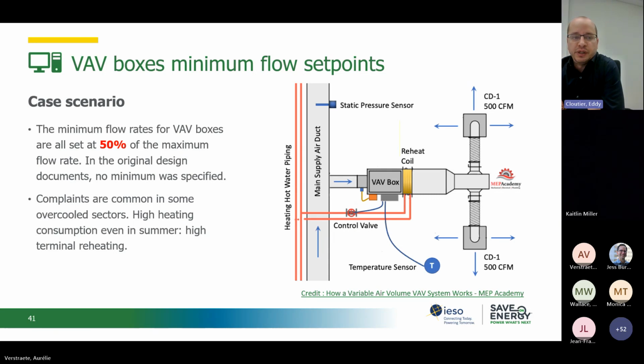Another type of measure that is related to controls, and this is one that we see really often in all types of building. Every VAV box has basically two set points: a maximum flow set point and a minimal flow set point. And it happens quite often that the minimal flow set point was not specified during the design. In that case, we had a building where all VAV boxes' minimum set points were fixed at 50% of the maximum, which is relatively and usually too high for the needs of the occupants and the air quality.